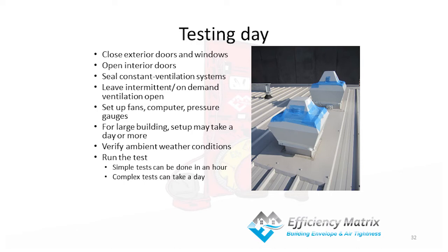On the test day, all openings need to be prepared, constant extraction needs to be sealed, access provided, and preferably the mechanical installer should be present. If test results are not what we expected, we need to do troubleshooting to locate leaks. In most cases it's something to do with the mechanical system — dampers not properly shut, allowing a lot of air to rush out — which gives the building a worse result. Having the installer present helps us go through things quickly.